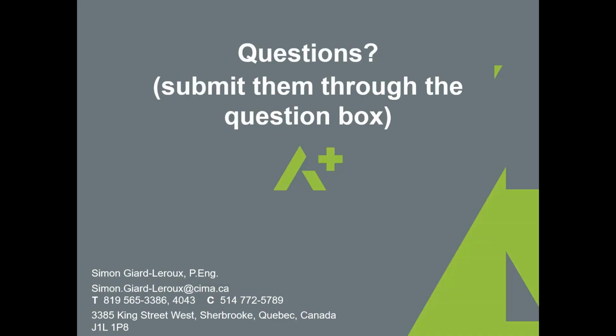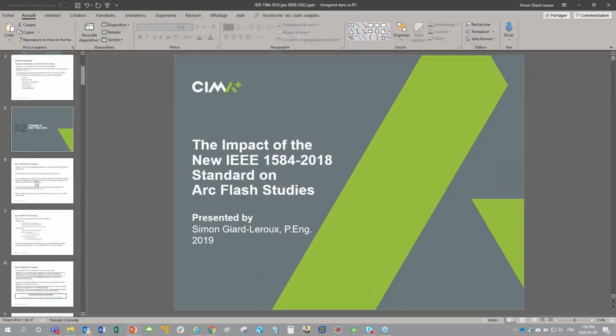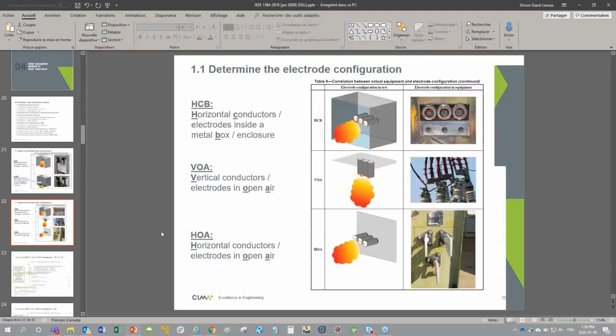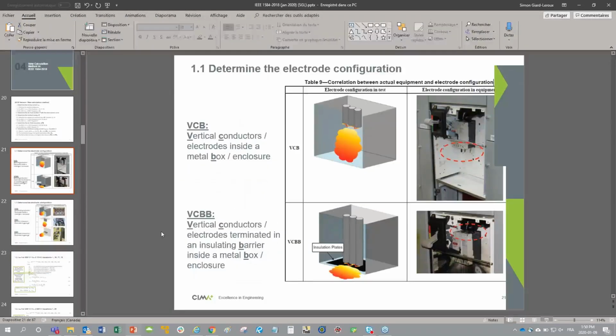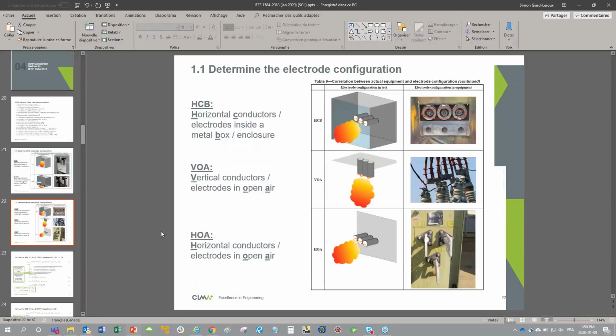Okay. What is the electrode configuration if fuses are being used? I'm sure he was referring to a specific image that you were looking at. Yeah, so I'll go back to the image. If you have fuses, there's no breaker to act as an insulating barrier. So VCBB does not apply, and VCB does not apply either. When you have fuses, I would suggest using HCB because the lugs that are holding the fuse will act as horizontal electrodes that will push the arc flash towards the worker.